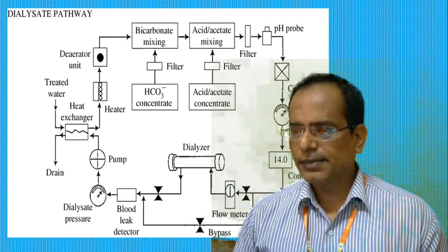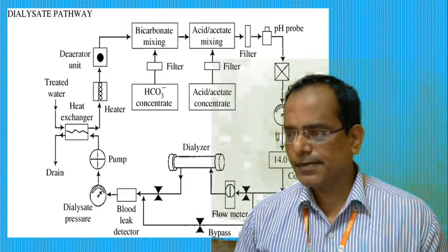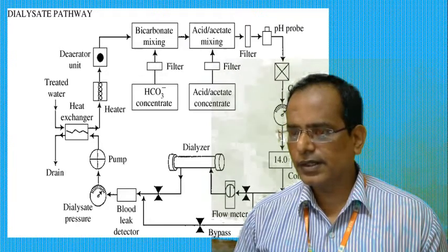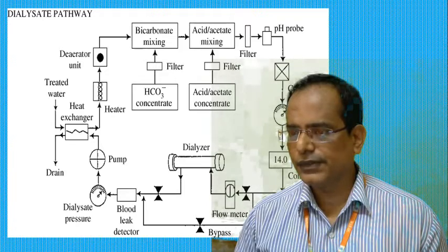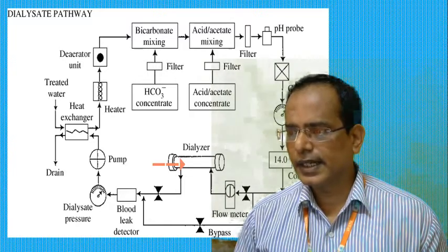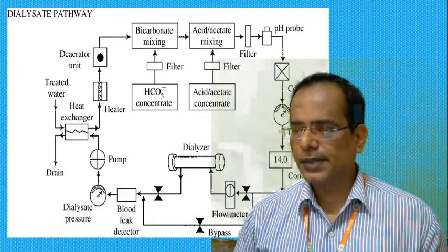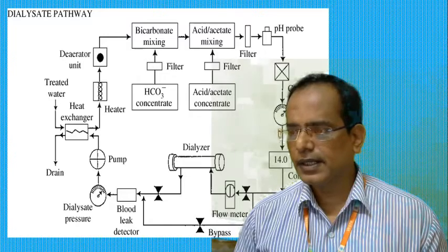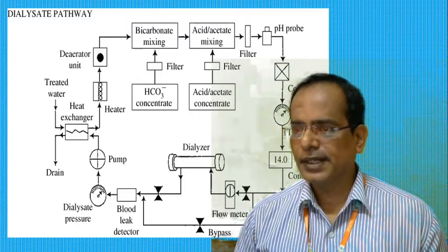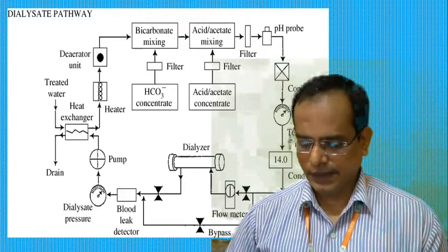The third type of exchange apparatus is a hollow fiber kidney. It consists of 10,000 to 15,000 hollow fibers with an internal diameter of approximately 0.2 mm and a length of approximately 150 mm, connected in parallel. So now we see that one.